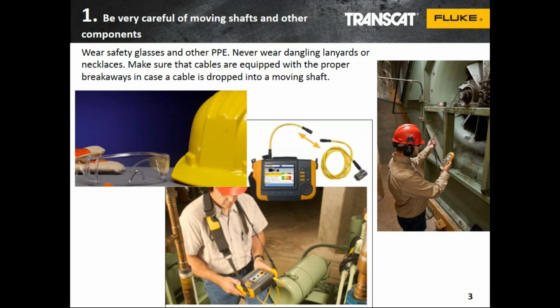Over the years, working in vibration analysis with vibration testers, one of the things you can see from these images is that when you have cables that you stick in close to bearings of machines to get data, we have the potential of a sensor and cable getting wrapped around a moving shaft.